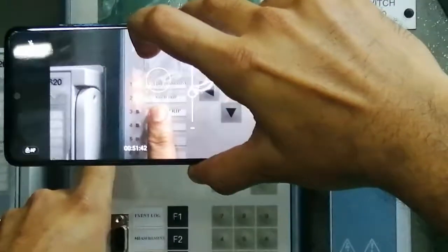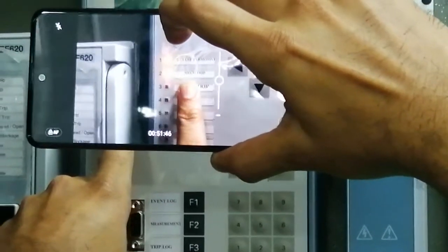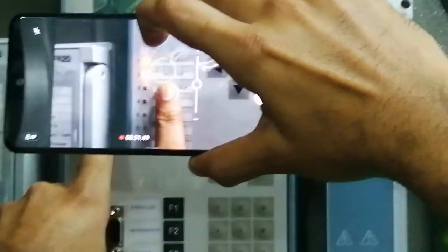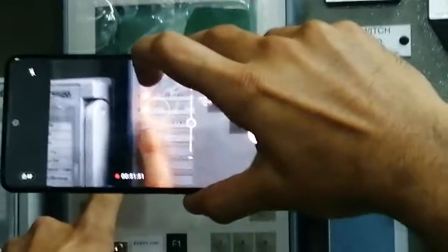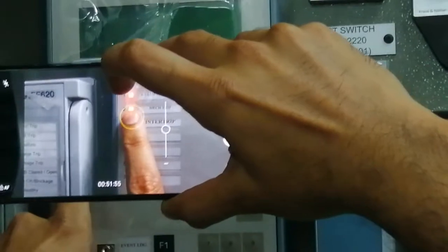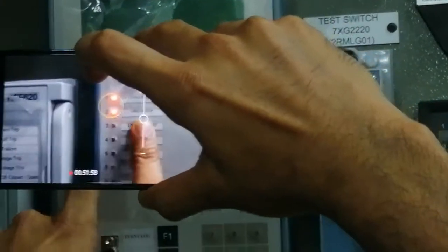So as you can see, let's see on the 132 kV side. We have this inter-trip one. Again, as you can see, the second LED we have configured for any mechanical transformer protection or breaker failure on 11 kV or any 11 kV earth fault protection. If we have any of these protections on the 11 kV side, then we will receive this on LED number 2 of the 132 kV protection. So you have seen. Now let's move to the next.